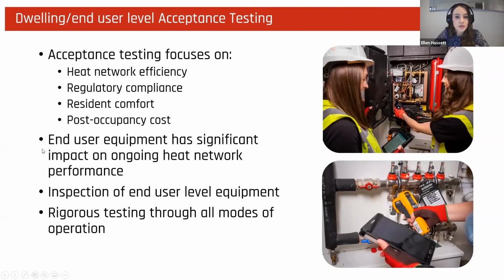So from a dwelling perspective, acceptance testing is designed to focus on 4 key areas throughout the process: heat network efficiency, regulatory compliance, resident comfort, and post-occupancy cost. A set of commissioning parameters and installation benchmarks are set early in the process for commissioning engineers to work towards. Initial acceptance testing is first carried out, ideally as soon as the first 10 to 20 dwellings are commissioned, to prevent the escalation of systemic issues in commissioning.